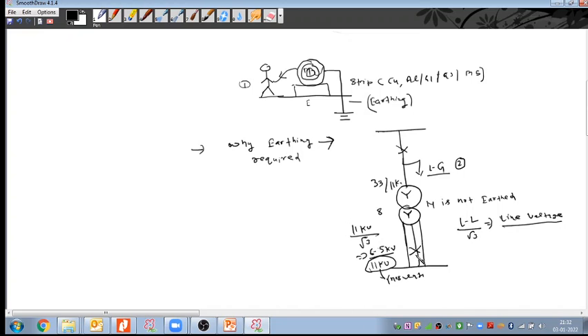So what is the problem? If the system is ungrounded, we understood three problems here. One, the equipment and the person are not safe. Second, the line to ground fault cannot be sensed. Third, the phase voltage will jump to the line voltage if the system is not grounded and not earthed. So this is the disadvantage.